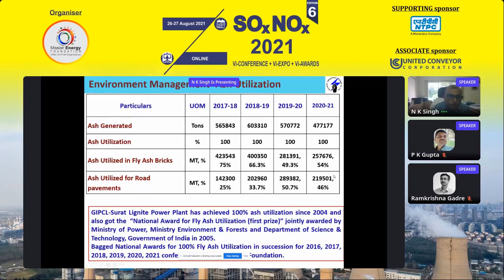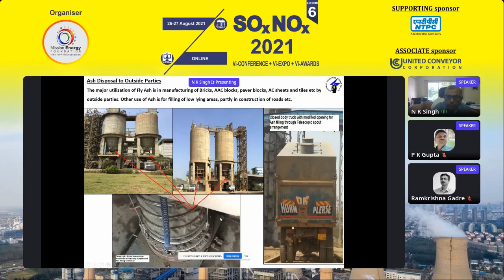Regarding environment management on the water side also, we have given the data for the last 3 years. On fly ash disposal, you can see the silo and the surrounding area. We are using 100% fly ash utilization, conveyed in the dry phase. We have a dense phase pneumatic system supplied by one of your sponsors, United Conveyor Corporation, and it is working well, with no dust nuisance. We only face problems with closed trucks, where there is some dust nuisance. So that is one area of concern.